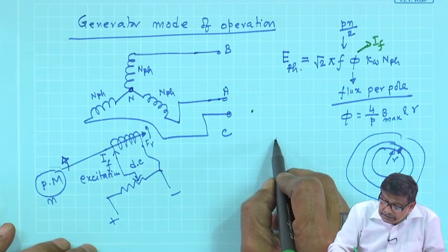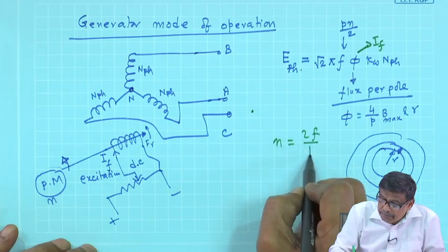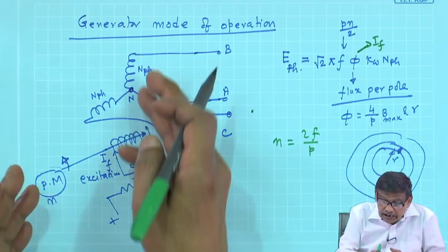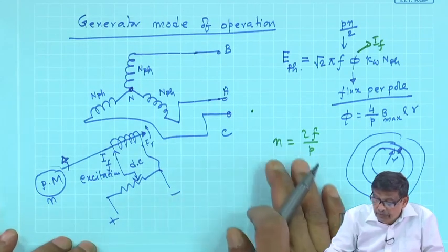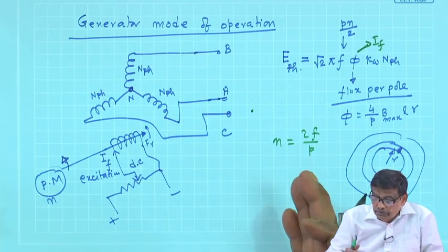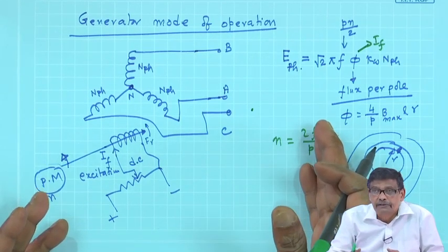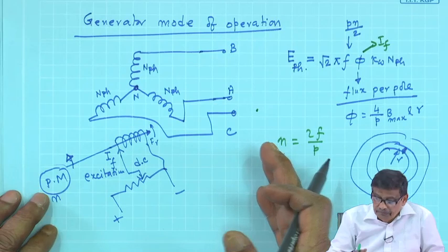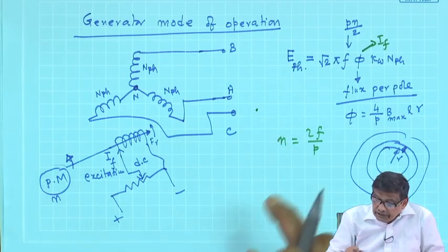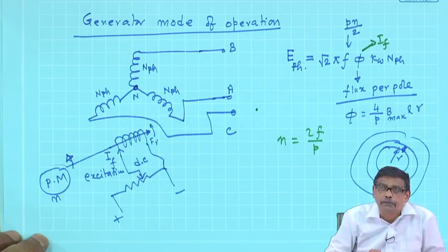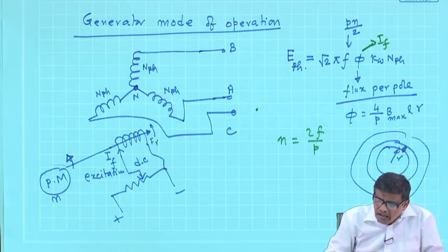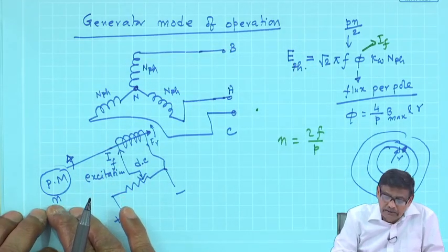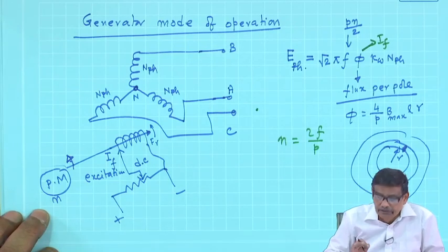You can generate any frequency: n = 2f/P. For example, for a 4-pole machine to generate 50 Hz, the speed is 1500 RPM. For a 2-pole machine, you must run the prime mover at 3000 RPM to generate 50 Hz. The frequency consideration decides what your prime mover's speed should be, if you know the number of poles of the generator.